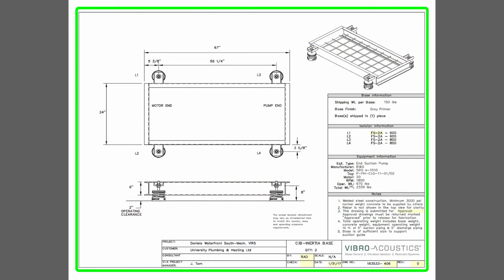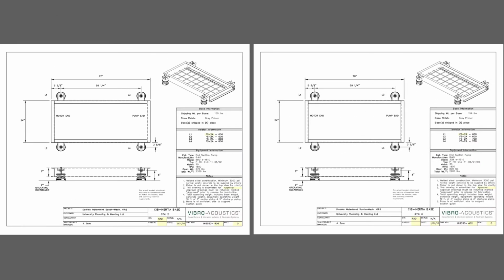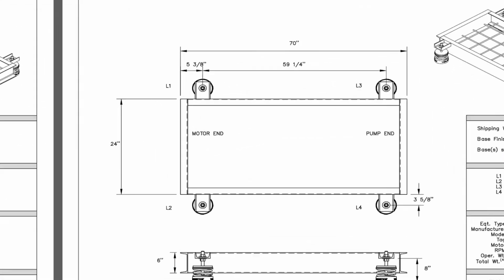Here's the inertia base drawing for the condenser water pumps, and this is the inertia base drawing for the chilled water pumps. Like the heating water pump inertia bases, these bases are also 6 inches deep with a 2-inch air gap and 4 2-inch deflection FS isolators. They differ only in their lengths, weight, and isolator selections. Note again that these drawings are schematic and not drawn to scale. As we'll see shortly, these bases are longer than the bases for the heating water pumps because they are supporting base-mounted end suction pumps and are sized to support both the pump and its suction diffuser elbow.